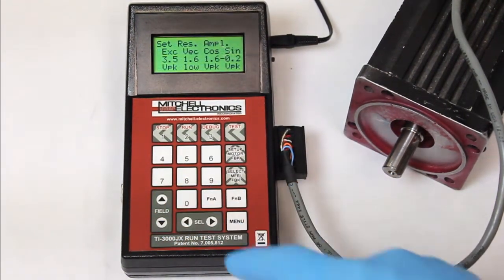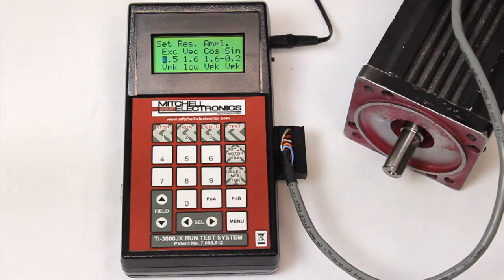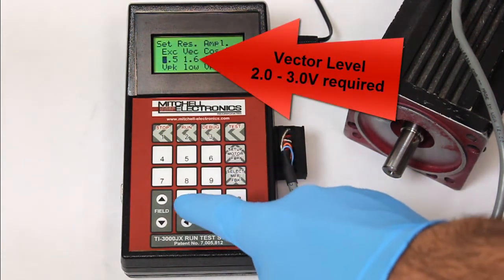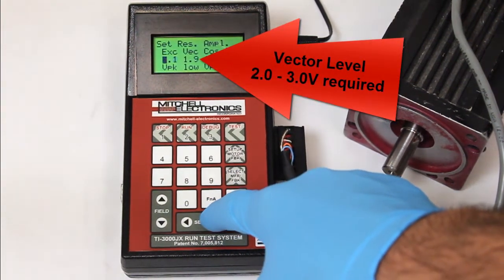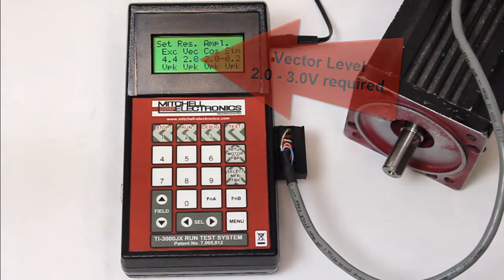Press the down arrow to access the excitation voltage selection. Adjust your excitation voltage until the vector level is between two to three volts. The vector level field will display low or high if out of range.